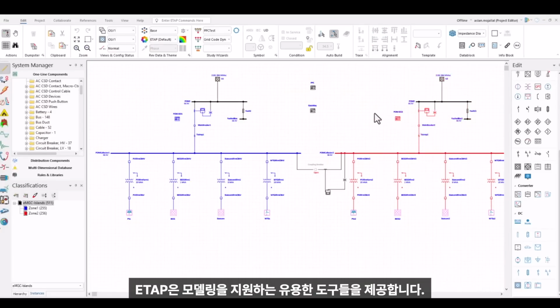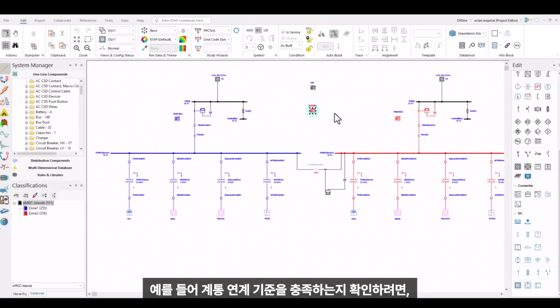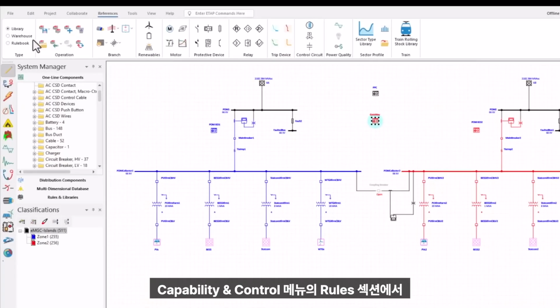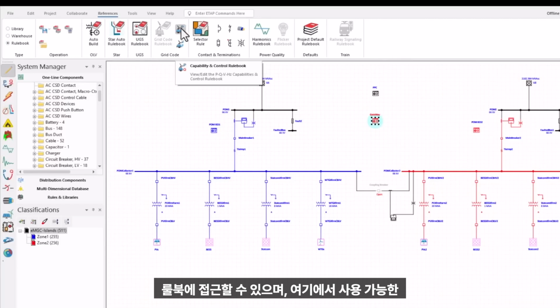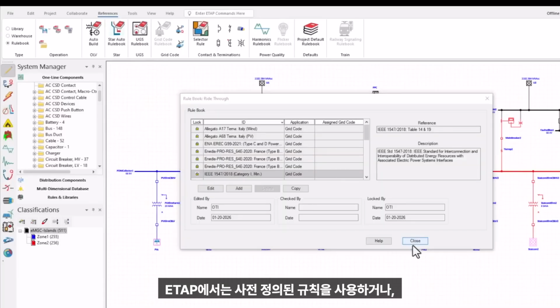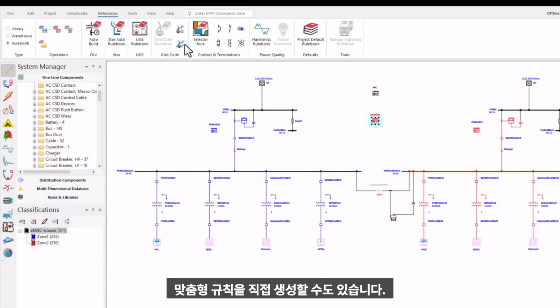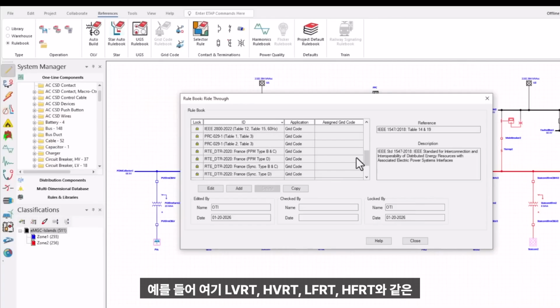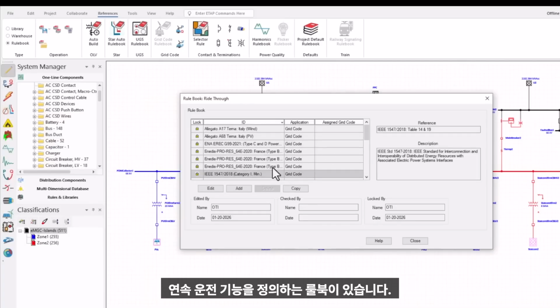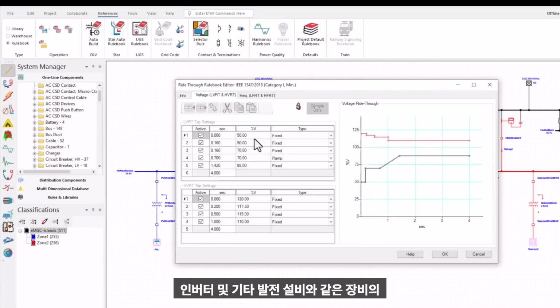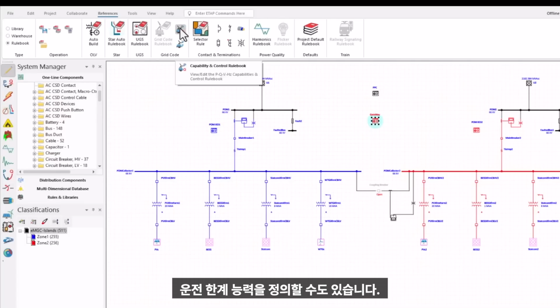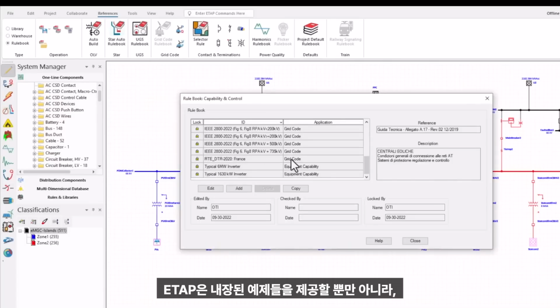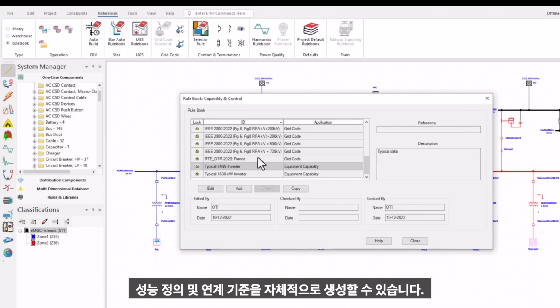ETAP also provides several useful tools to support this modeling stage. For instance, if you want to verify compliance with the grid code requirements, you can define those requirements in the rulebook. You can access the rulebook under the Rules section in Capability and Control, along with the available rule definitions. ETAP allows you either to use predefined rules or create custom rules for your own project requirements. For example, here we have a rulebook that defines ride-through capabilities such as LVRT, HVRT, LFRT, and HFRT. You can also define the capabilities of your equipment, such as inverters and other plant assets. ETAP includes built-in examples, but it also gives you the flexibility to create your own capability definitions and grid code requirements.